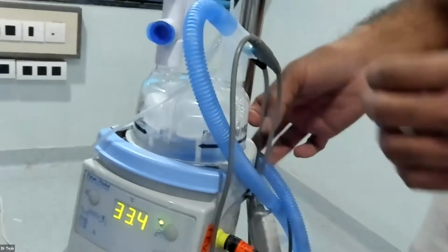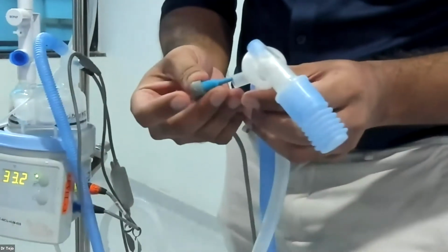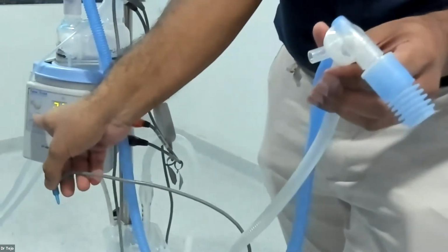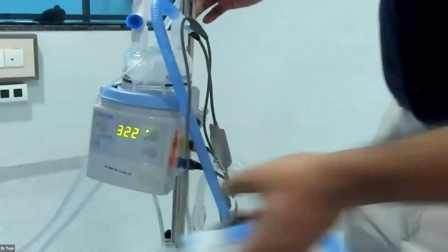When we come to the airway probe alarm, this also comes here. I will show this in the diagram once again. This alarm will also take around 20 minutes to come. It is not coming now, but it usually comes here, and it also takes around 20 minutes to get the alarm.